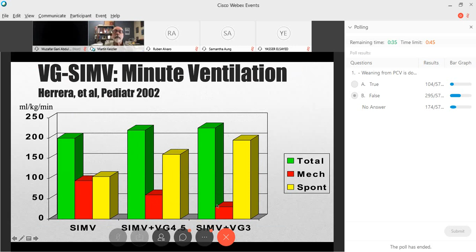I'm going to skip over it because we are kind of out of time. But if you lower the pressure too much and make the baby do all the work, this is what you're going to see. Here's a scenario where the baby's tidal volume setting is less than what this particular baby needs. The baby generates a tidal volume with their own respiratory effort greater than the set tidal volume. Pressure comes down, down, down until it becomes essentially PEEP. And so this baby is getting no help from the ventilator.